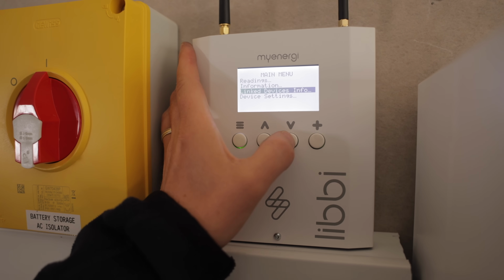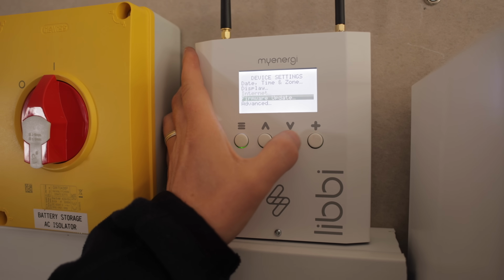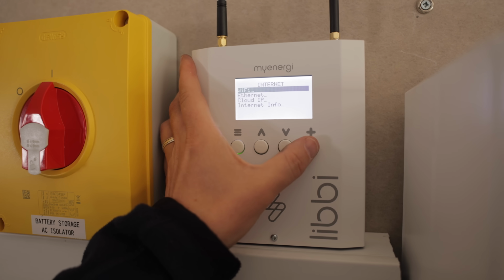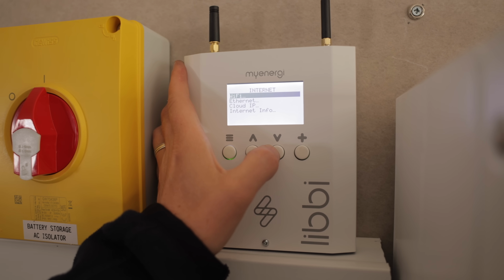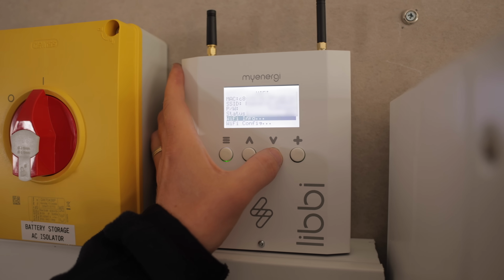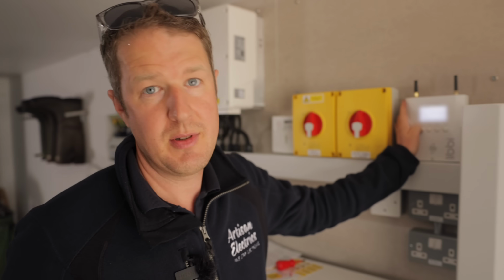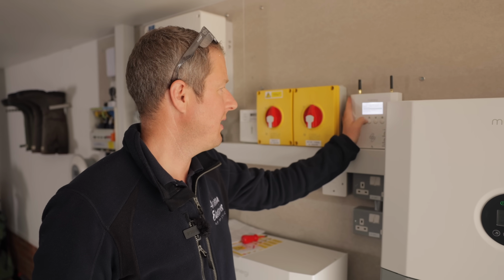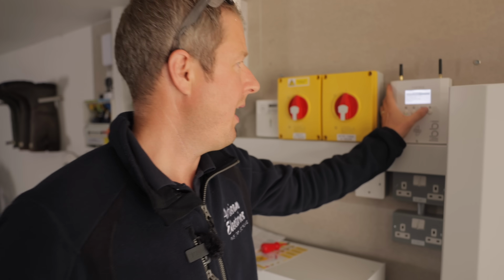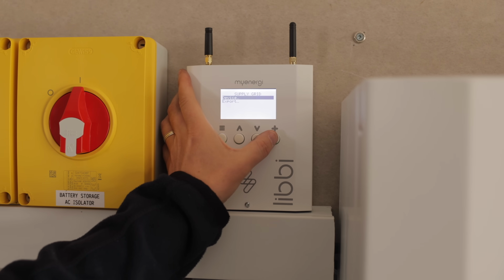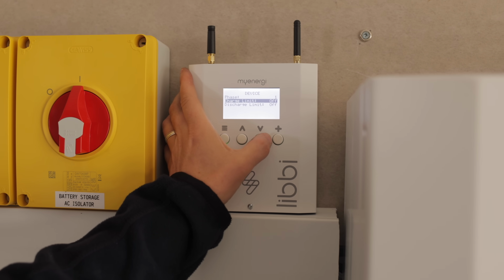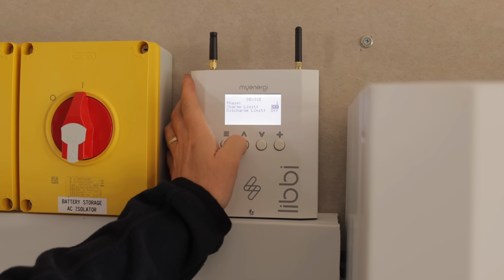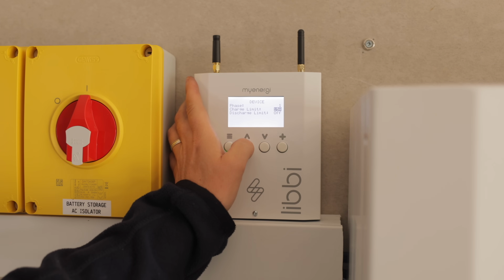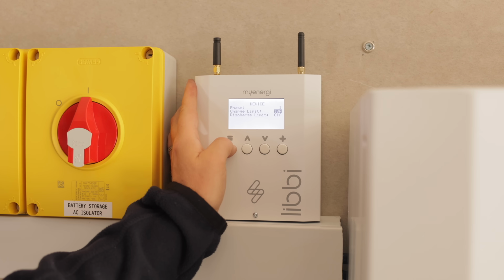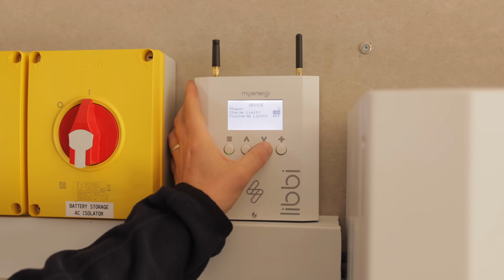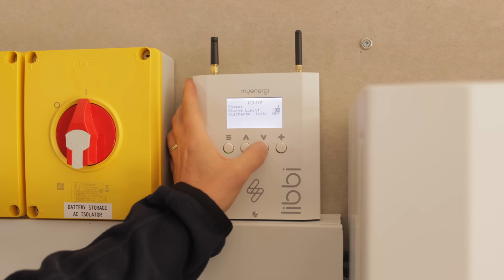What we need to do sometimes is in device settings, we need to go to internet, and we need to set Wi-Fi. So if you don't have a hardwired Ethernet connection, then you will need to set up the Wi-Fi, and you can just do that using Wi-Fi config and pair it up to the local Wi-Fi network. Other things that you need to think about are in the advanced menu, supply grid. You can set a device limit, so you can set a charge and discharge limit if you want to. So for example, charge limit 1 amp all the way up to 18 amps, 5 kilowatts, and then you can set a discharge limit as well. So we won't set these, but it's an option if you want to.